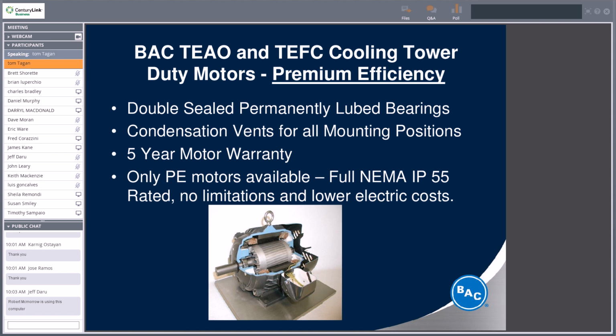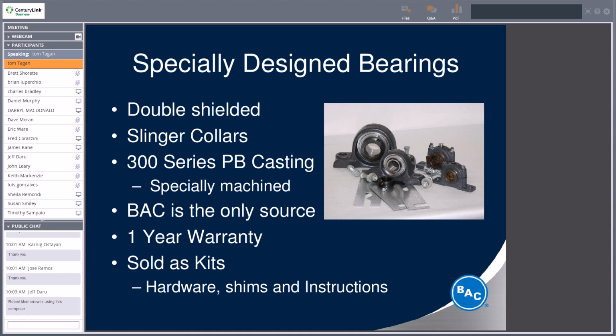I mentioned the motors are specifically designed for cooling tower service, designed so that water's not going to stay in there. If anybody's been inside of a cooling tower, it's a pretty violent atmosphere. It's hurricane conditions. We have very high winds, and we're introducing water to it. So you need bearings, bushings, fan shafts, fan motors. You need everything that can withstand a pretty violent corrosive atmosphere. Specially designed bearings, again, everything's done to try to prolong the life of them. Even though parts is an important business for us, we still need these things to last quite a while to keep our reputation in good standing. So, again, everything's specially designed.